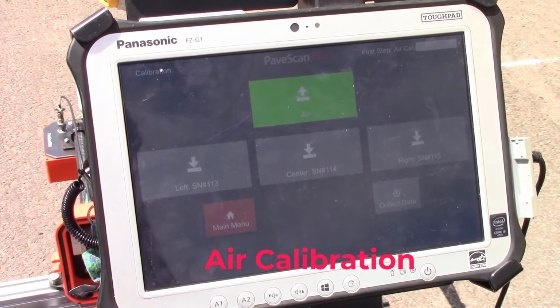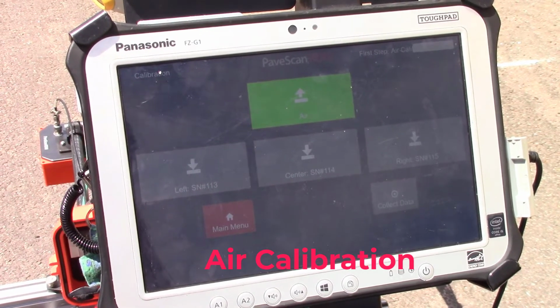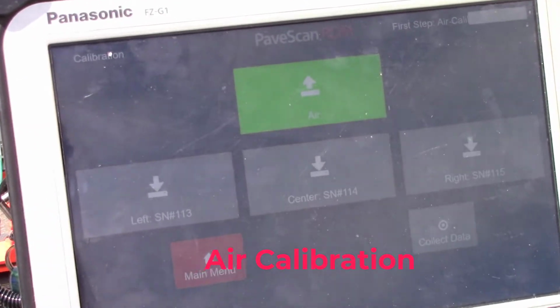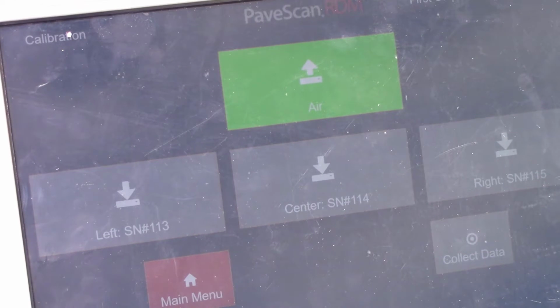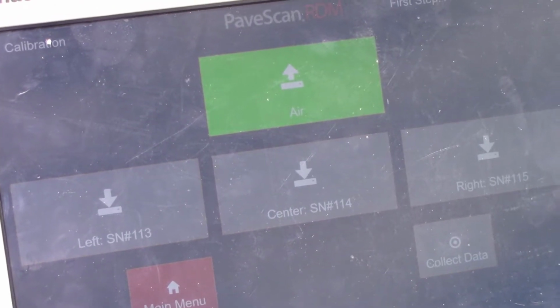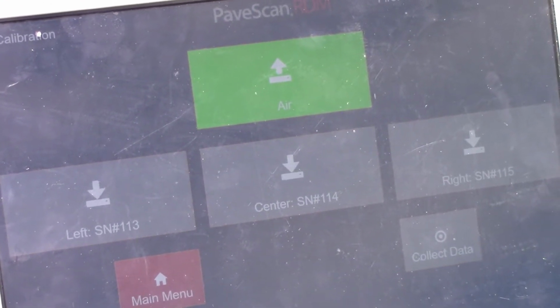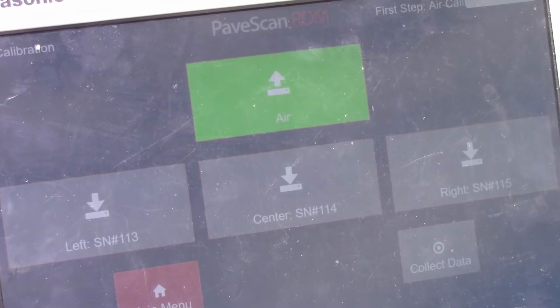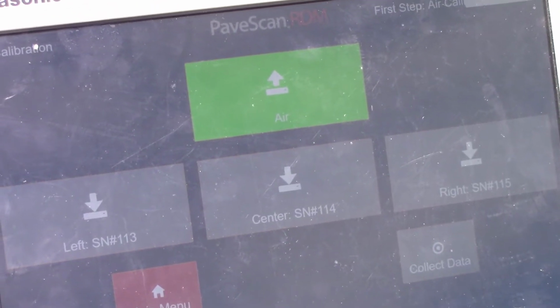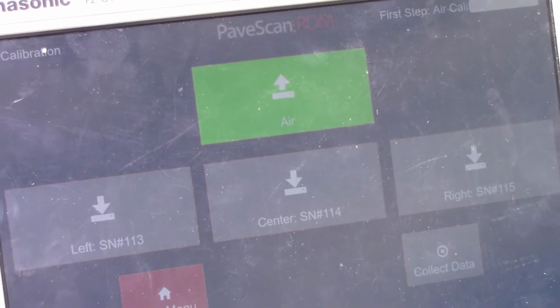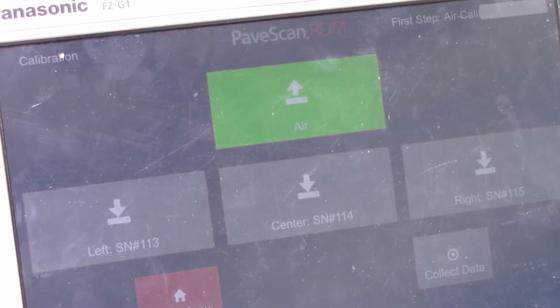You'll now notice that the Air button is highlighted in green. This is the page that allows us to do our air and metal calibration. The air calibration is first, which means we're going to want to take our GPR sensors and rotate them so that they're facing toward the sky.